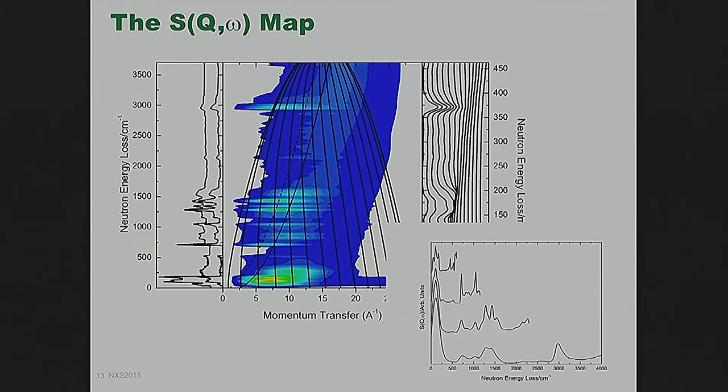And that is very important when you try to track the amount of hydrogen in a material, because the very design of VISION allows you to count all the intensity that goes exactly on top of mass one, because the mass of the neutron and the mass of the proton are almost equal. So everything that VISION counts, if it's hydrogen, it will measure it. Whereas if you do it with a direct geometry instrument, you are not sure.